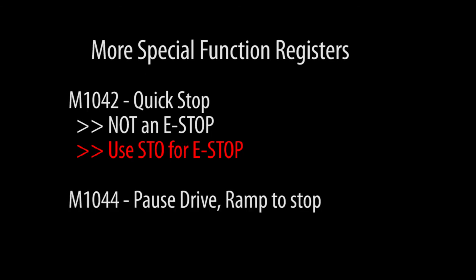Enabling register 1044 pauses whatever the drive is doing and uses the current deceleration parameters to ramp the speed of the motor down. When you disable 1044, the drive ramps back up to speed and continues on its way.